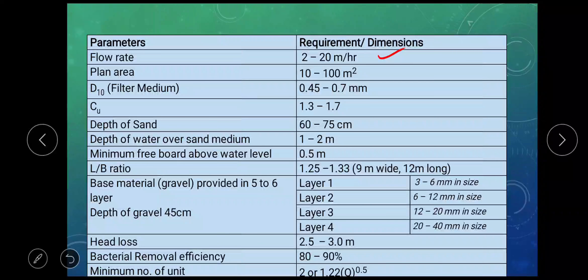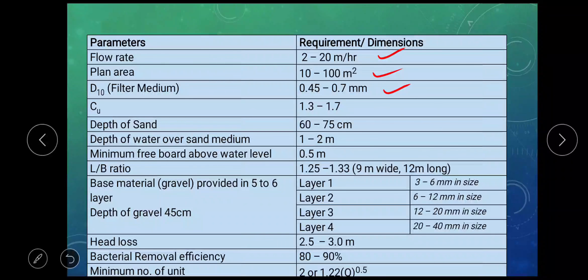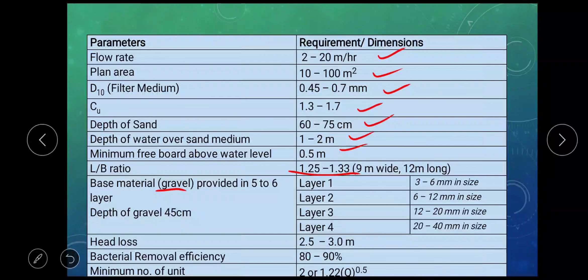Surface area for rapid sand filter may vary from 10 to 100 square meter; however, this value for the slow sand filter may range from 100 to 2000 square meter. Effective size of the sand grain may vary from 0.45 to 0.7 millimeter; however, for the slow sand filter this value may vary from 0.2 to 0.35 mm. Coefficient of uniformity may vary from 1.3 to 1.7. Depth of the sand may vary from 60 to 75 centimeter. Depth of water over sand layer may vary from 1 to 2 meter. Freeboard of 0.5 meter is provided. Length to width ratio may vary from 1.25 to 1.33. Base material, that is gravel, may be provided in 5 to 6 layers for good distribution of wash water.